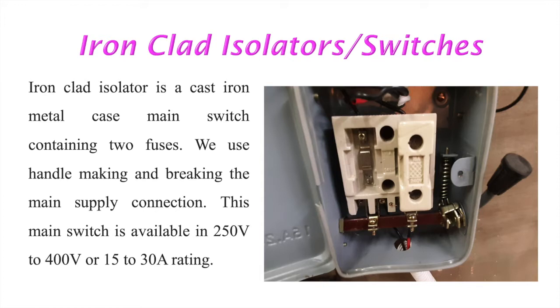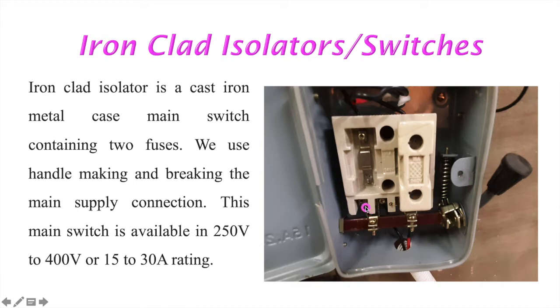Another important component is the iron clad isolator. The body of this isolator is made by iron or cast iron, which is why it is called iron clad. The isolator is actually the main switch. When your domestic connection is connected from the supply via this main switch, it is operated manually using a lever — up to engage, down to disengage. Two KitKat fuses are used here to control current overflow.